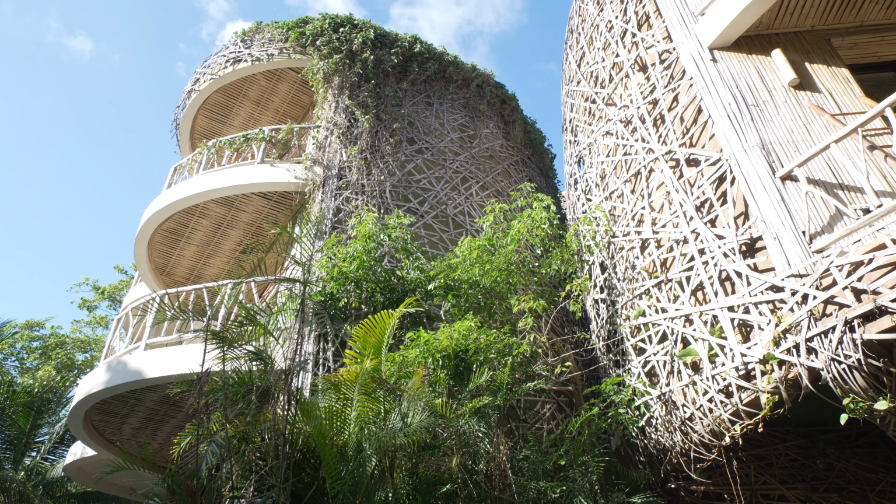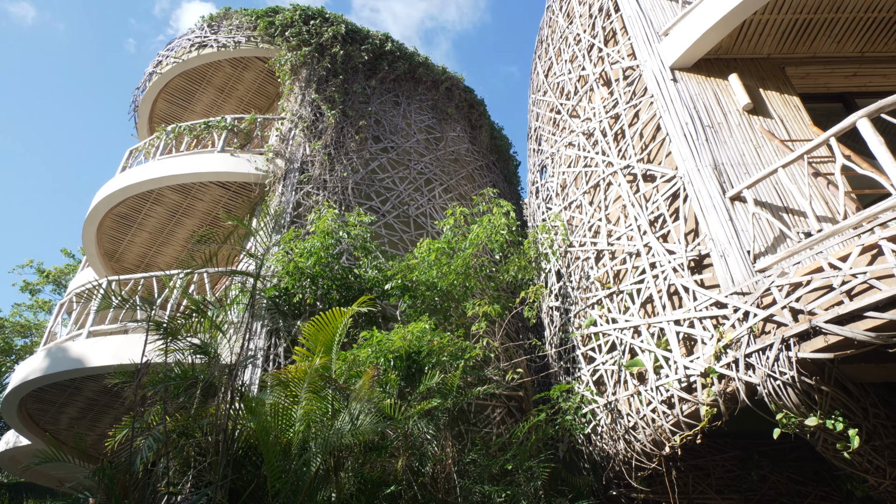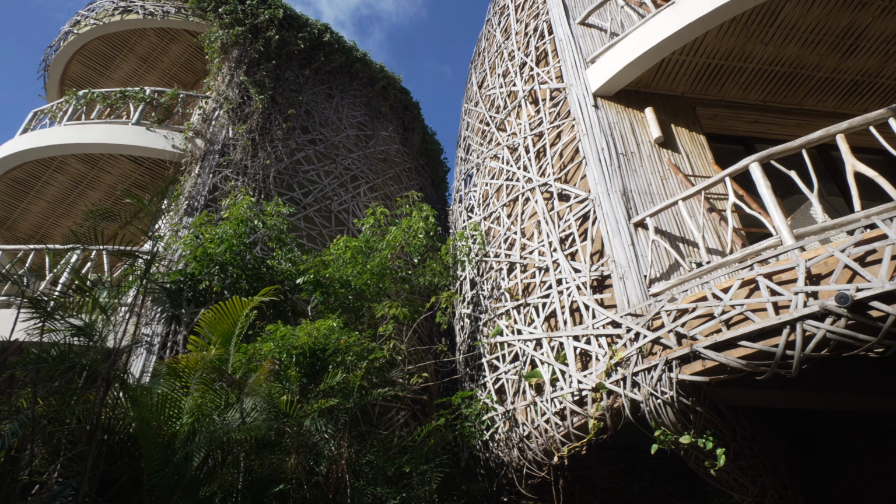3rd, we have a skin. It's a bamboo skin that wraps the buildings, and then we grow plants over them, creating a completely living wall over the buildings. Now this is going to take a few years to complete, but what this essentially does is lock a warm pocket of air between the concrete building and the actual skin, in turn naturally cooling the building by up to 3 to 5 degrees centigrade. It doesn't sound like a lot, but it makes an awful lot of difference on your energy bill. And also when it's 40 degrees centigrade outside, 4 or 5 degrees is something.